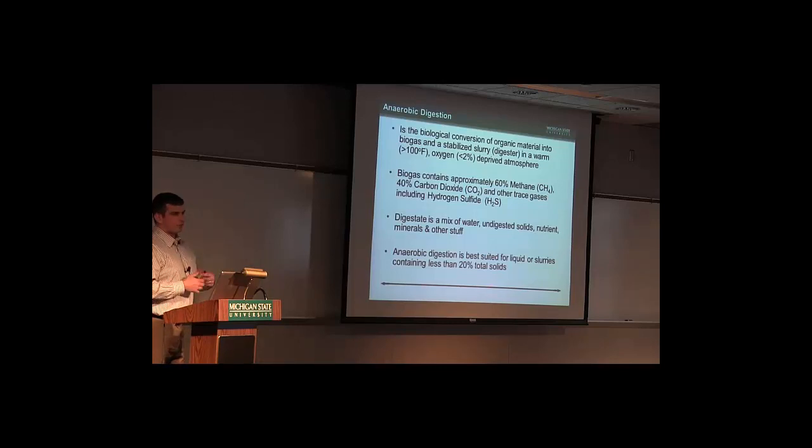And as I said, it is best suited for slurries or for liquids. We can do digestion up to maybe 30% solids, but once you get above 30% solids, there are other waste to resource technologies that are probably more appropriate. And for the most part, digesters are going to operate between 5 and 15% solids.